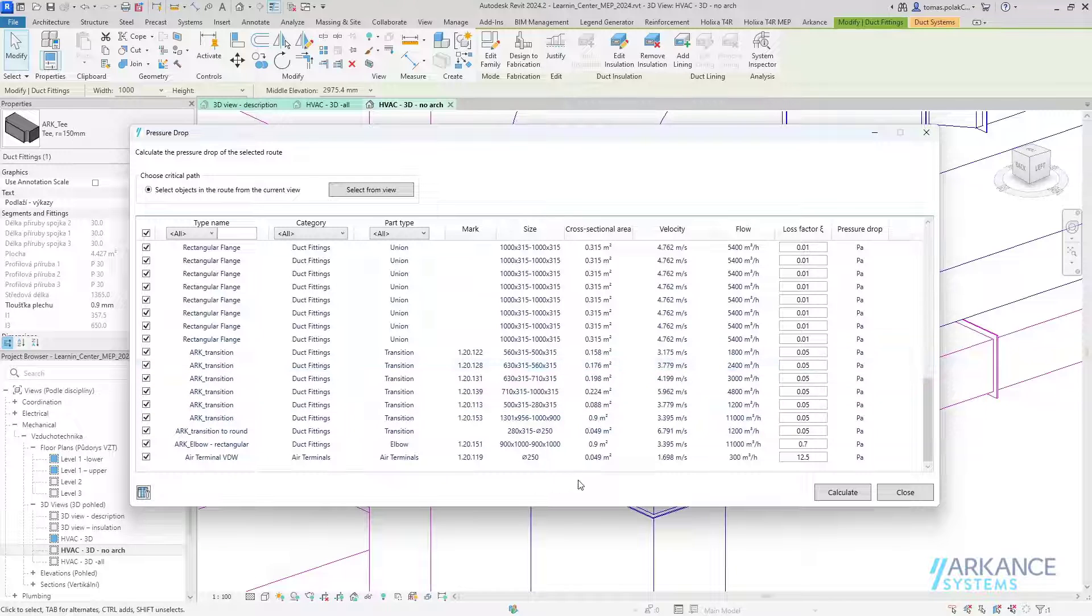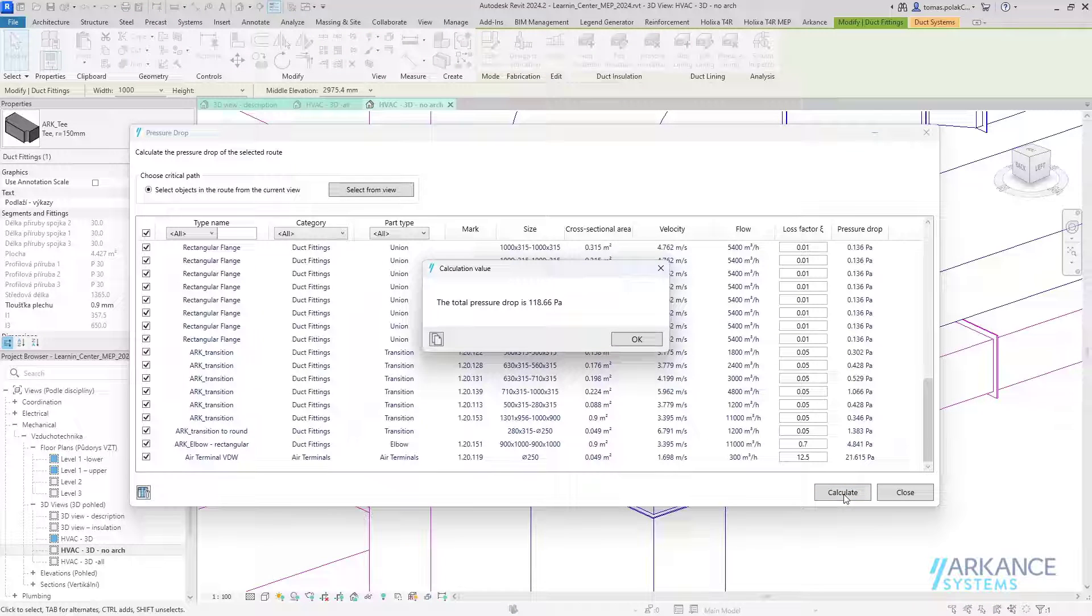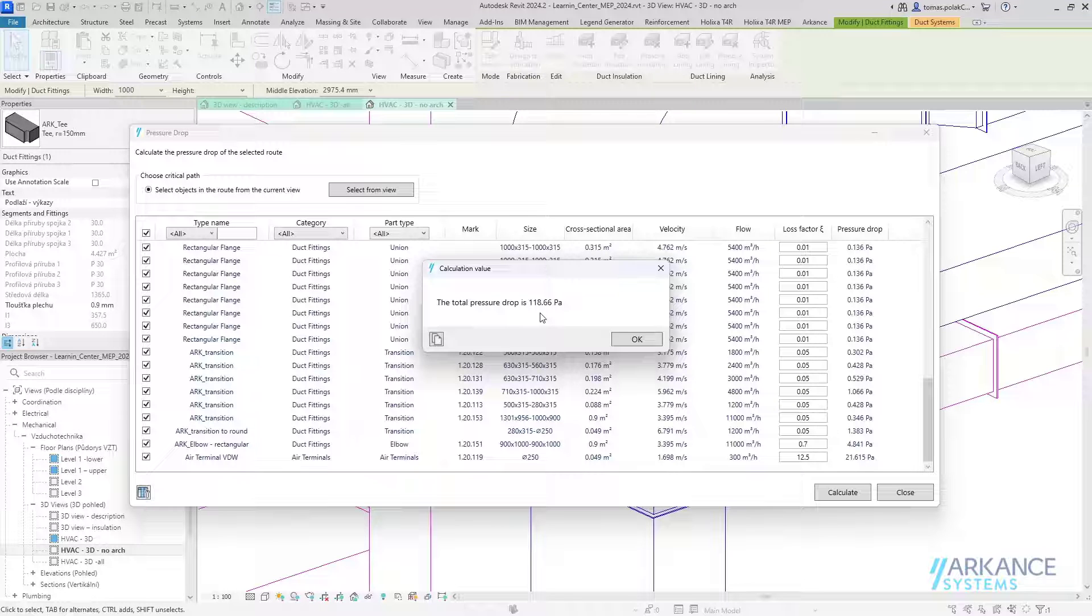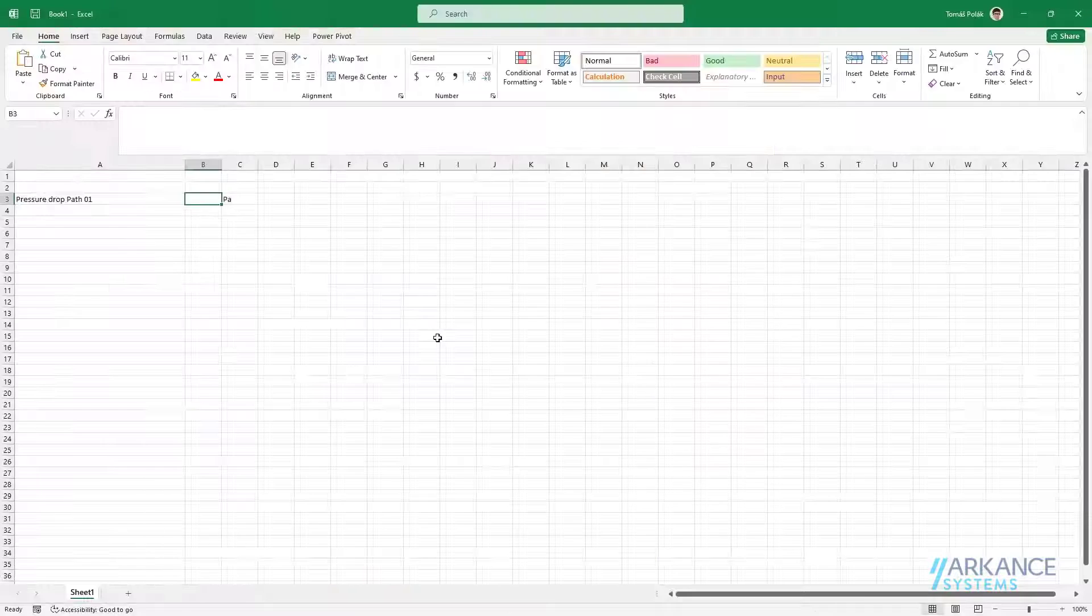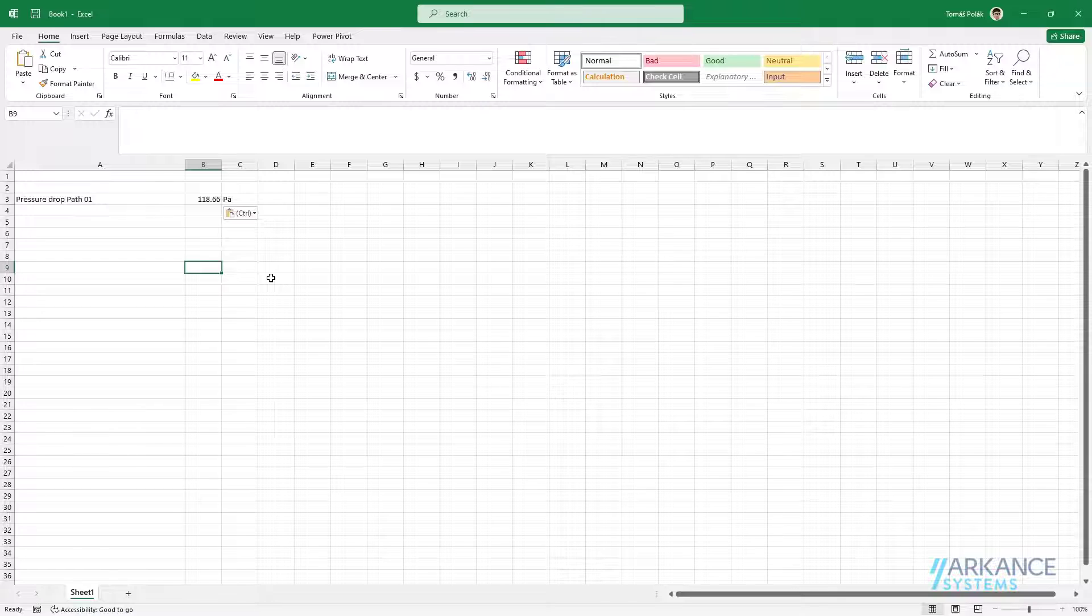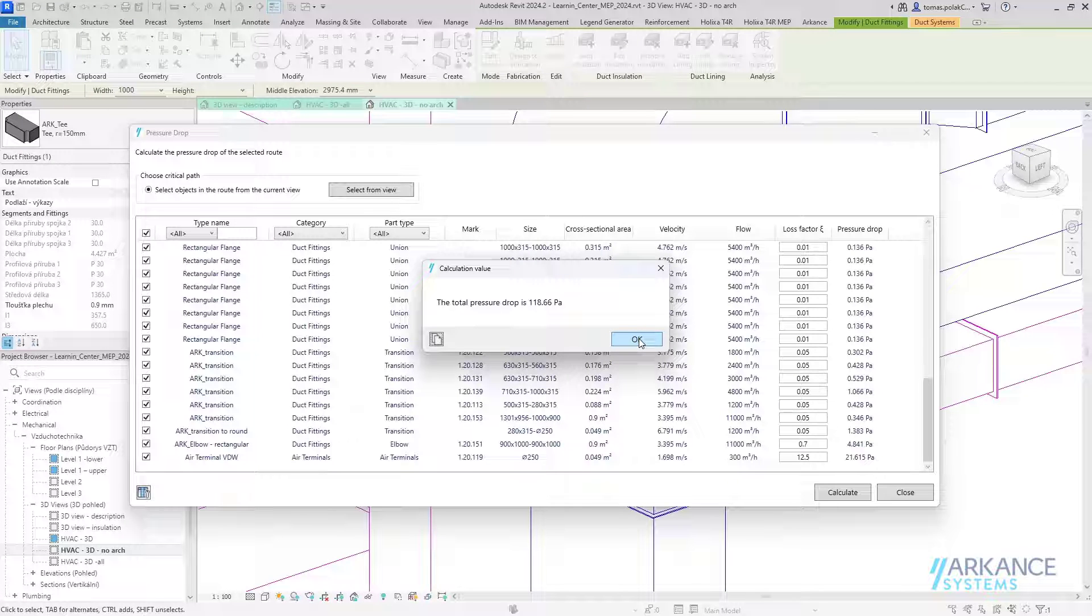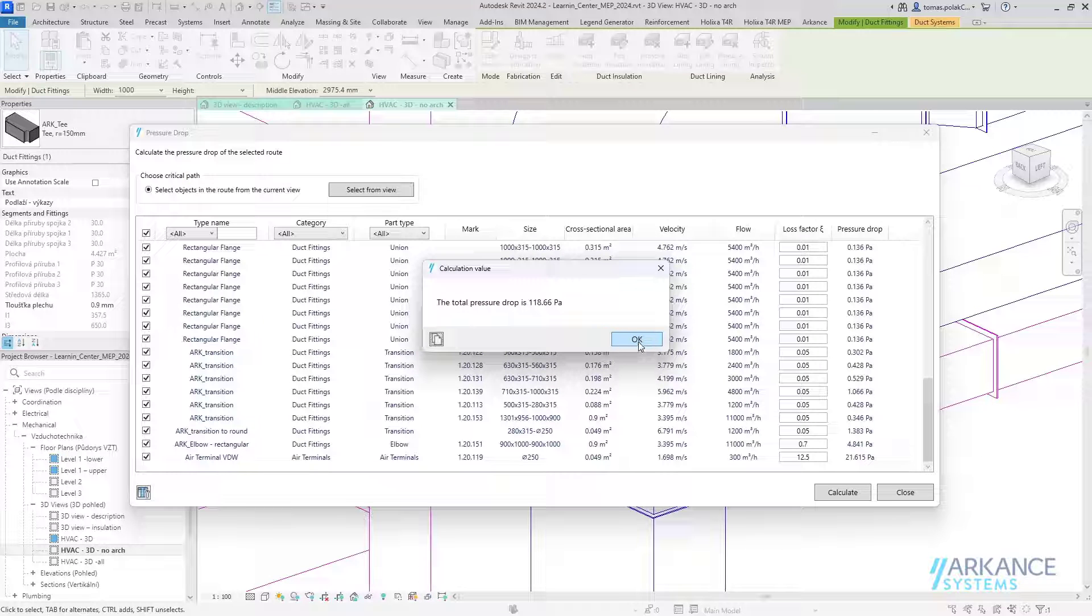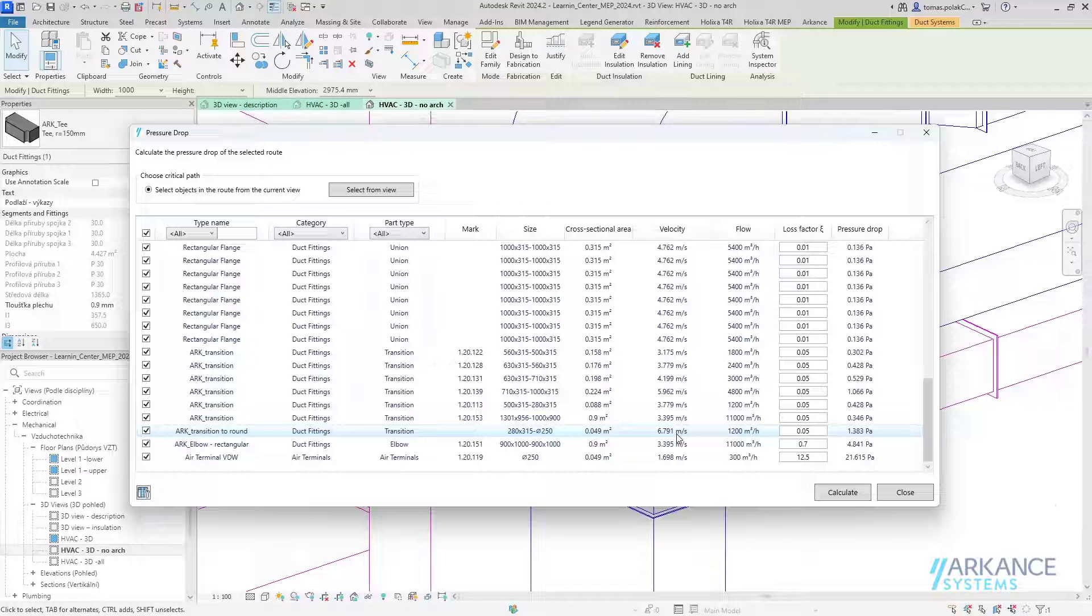We can calculate the pressure drop of the selected path simply by clicking the calculate button. The calculation tells us the pressure drop of the selected path, which is here. Darcy-Weisbach equation is used for the pressure drop calculation. The calculated value can be copied into the clipboard and then easily inserted into software of your choice. Now we are back in Revit. This is the basic calculation of the pressure drop.